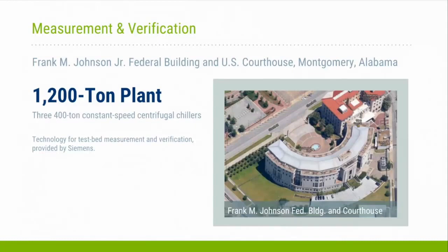The chill water plant consists of three 400-ton constant speed centrifugal chillers, and as we're going to find out in this discussion, VFDs were applied to everything except for the chillers and the compressor motors that serve the chillers. Let's go to the next slide, please.